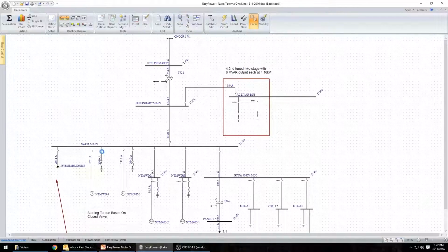In fact, I can open these capacitor branches and simulate what would typically be going on if these were operational. You can see that the distortion has dropped to 2%. So this would represent a situation in which we're starting one of these motors. We have an RVSS in operation, and the actiVAR is in operation also. And you can see that during starting, the actiVAR actually will act to reduce voltage distortion and current distortion into the bank and into the system for that matter.